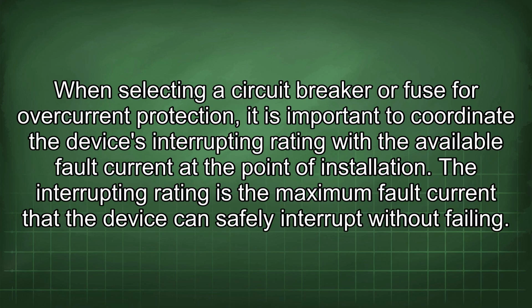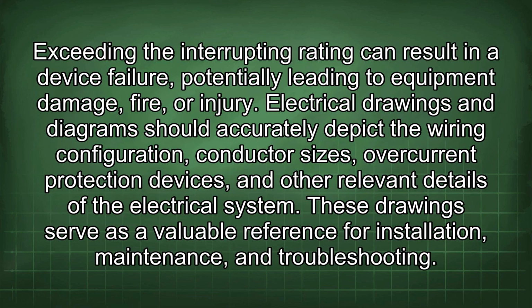When selecting a circuit breaker or fuse for overcurrent protection, it is important to coordinate the device's interrupting rating with the available fault current at the point of installation. The interrupting rating is the maximum fault current that the device can safely interrupt without failing. Exceeding the interrupting rating can result in a device failure, potentially leading to equipment damage, fire, or injury.